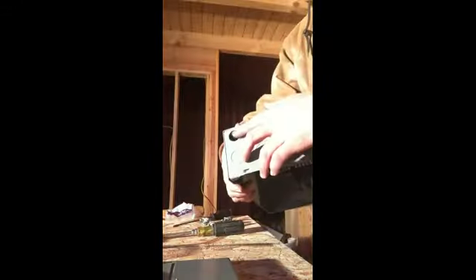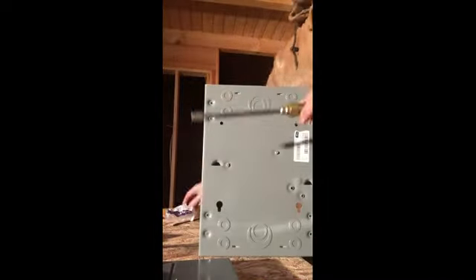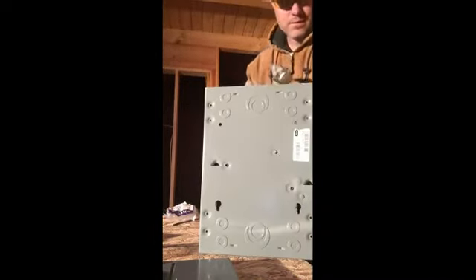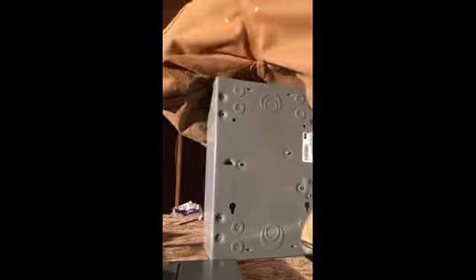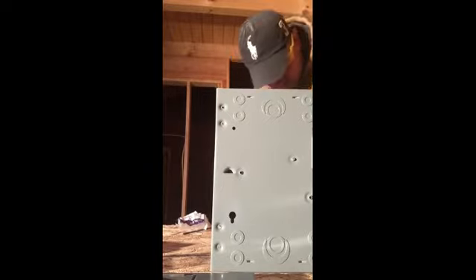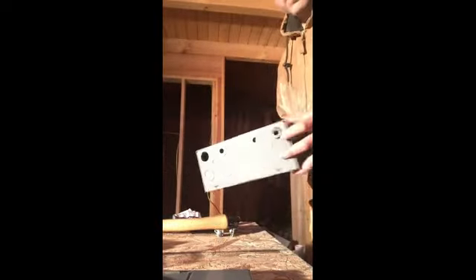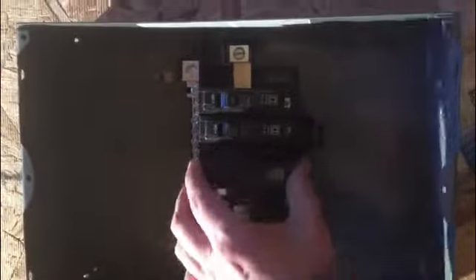You need to punch out the top and the sides of the panel box where you want the individual circuit runs to enter. Insert the panel box connectors first before you insert the wire into the panel box. You must strip down the wires from the plastic coating which runs through the studs. Now you should see a black wire, white wire, and bare wire if it's 12-2 wire. If it's 12-3 wire, you'll see a black wire, bare wire, white wire, and a red wire. Both black and red are hot wires.